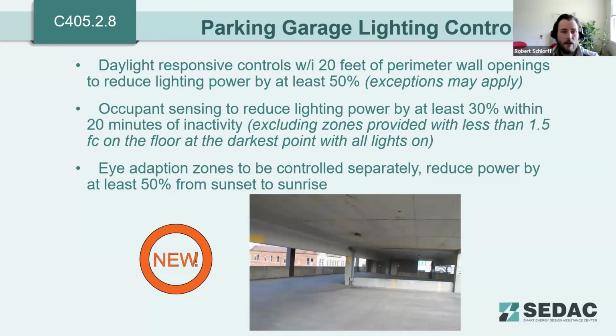Occupant sensing must reduce lighting power throughout the parking garage by at least 30% within 20 minutes of inactivity. This excludes zones provided with less than 1.5 foot candles on the floor at the darkest point. Again, tying back to what I said about corridors earlier, the code is keeping safety of occupants in mind here, making sure that those particularly dark spaces aren't made darker by occupant sensing controls. And then, as I said on the last slide, eye adaptation zones for the entrances and exits of parking garages must be controlled separately and must reduce their power by at least 50% from sunset to sunrise. So those have specific controls for the eye adaptation zones at entrances and exits.